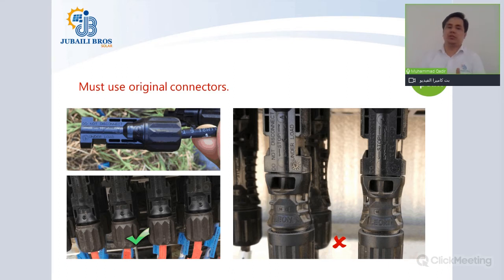So you are advised to use an Amphenol connector with an Amphenol connector, not from Jubaili or Weidmüller or any other third party. Similarly, for the MC4, you should use an MC4 connector. If you are missing one, try to procure an MC4 connector from the market, not from any other third party. In these scenarios, if HUAWEI finds out, it may void the warranty of the inverter. So please try to use same-manufacturer connectors for connecting the joints to the inverter.